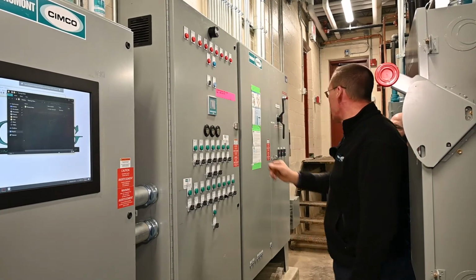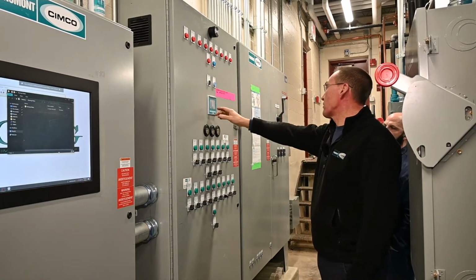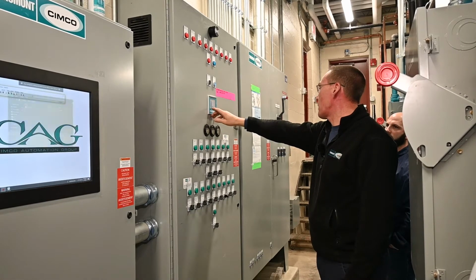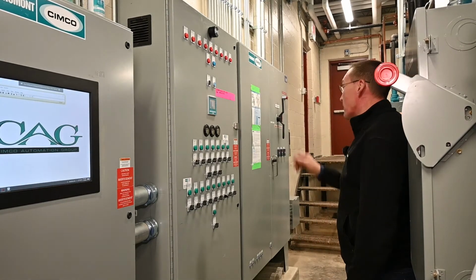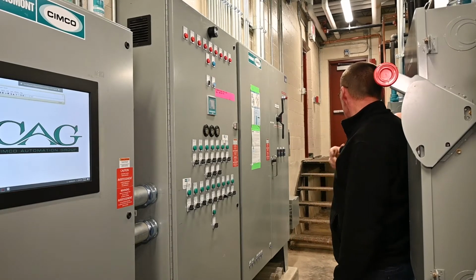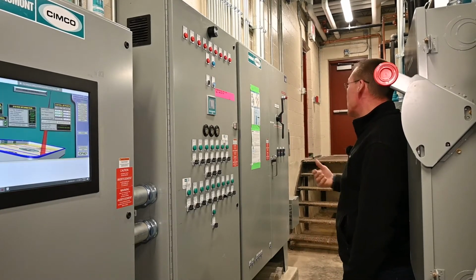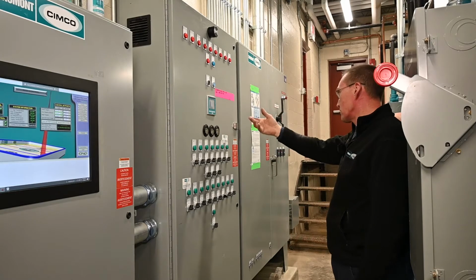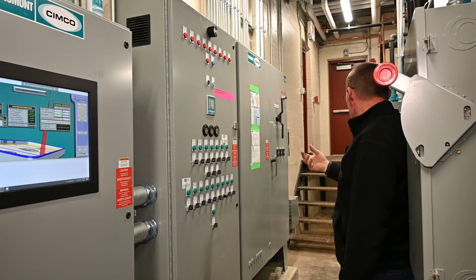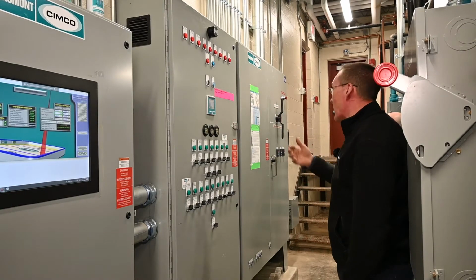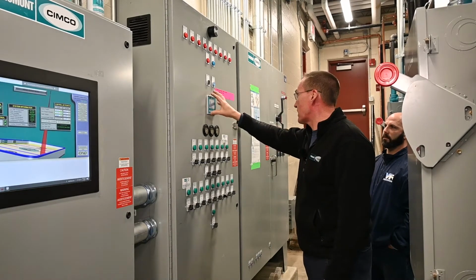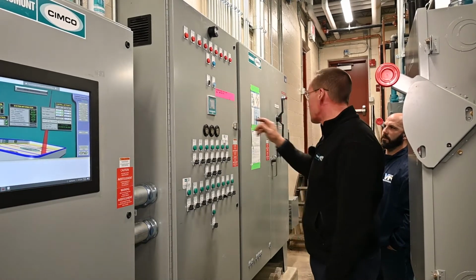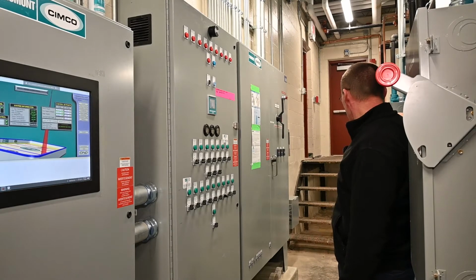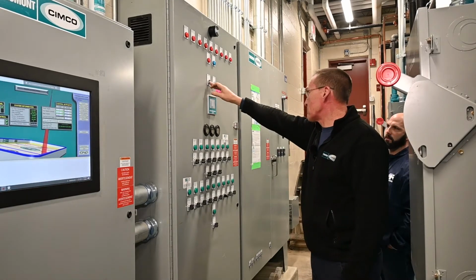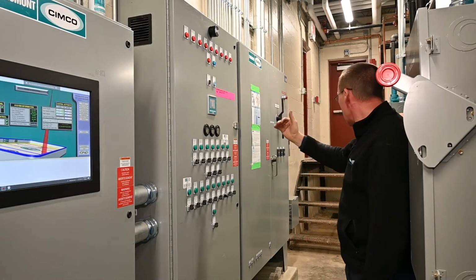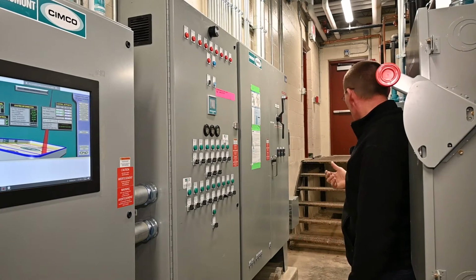You'll press the magnifying glass and it would ask you, right here in blue and white, to acknowledge. You have to acknowledge the alarm once you've talked to us and we say, okay, hey, I need you to do this, and you would go ahead and do that, and then we would be able to restart the system. Then that unlatches everything. It clears the alarm within here so that, as long as it's not a physical failure of a compressor component, you would be able to reset the alarm. It would clear it, and we could restart the compressor again.